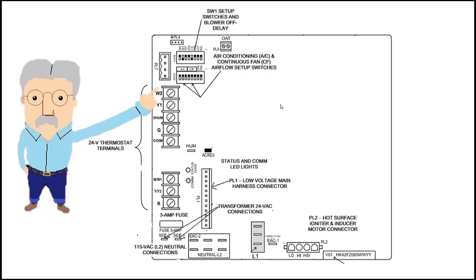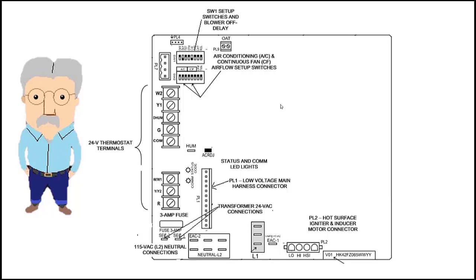Then we have our 24 volt thermostat terminals. We go from our R, our Y terminals, our W terminals, our G terminal, and our C or common terminal. We have our 24 volt 3 amp fuse. Here we have our 24 volt connections for our transformer. We have our status lights, our 12 pin connector, our high voltage or 120 volt neutral bus, the hot bus. And then we have a 4 pin connector that connects our draft inducer fan and our hot surface igniter.